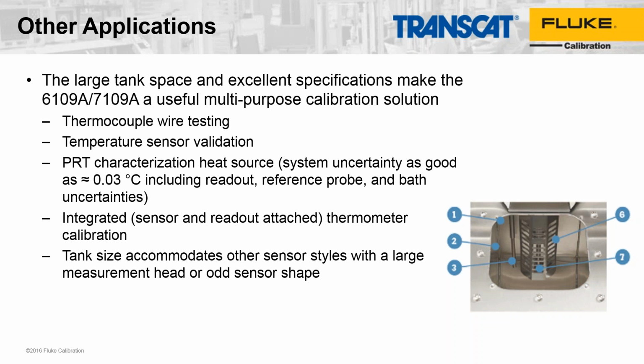Some of the other applications that we see customers using these for is thermocouple wire testing, sensor validation, because you can load up a lot of small sensors in this tank and validate the sensors. You can also use it for traditional characterization of temperature sensors like PRTs and thermistors. You can calibrate integrated thermometers like the Fluke stick thermometer, for example. In general, the tank is large enough to accommodate a lot of these explosion-proof type transmitter heads or other types of industrial temperature sensor heads.